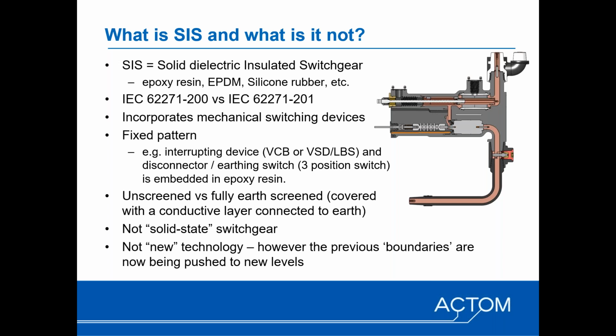Then we've spoken about -200 as well as -201, and the important thing is that as per the title and definition, -200 covers switchgear that is housed in the metal enclosure, and 201 is switchgear that does not necessarily have a metal enclosure, but is effectively insulation enclosed, and we will show some of those examples. It's important to realize that solid dielectric can fit into both categories, and that it doesn't necessarily fall under -201. In fact, it falls well into the -200 metal enclosed switchgear series of standards.